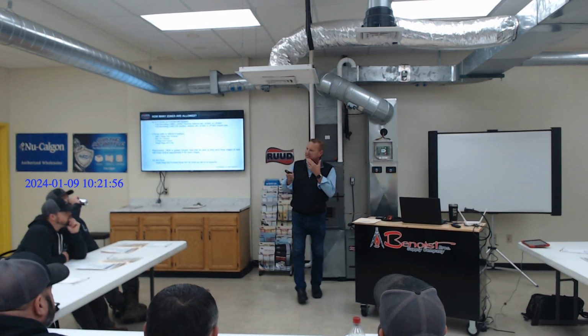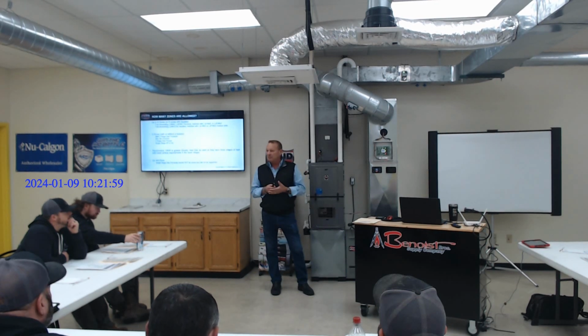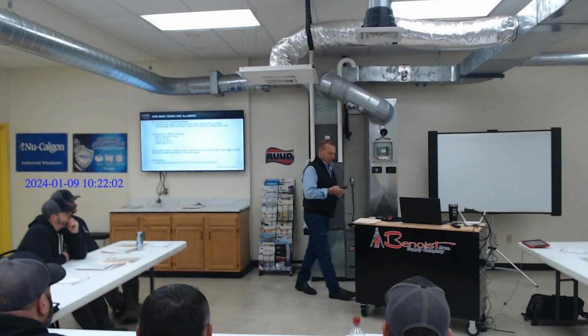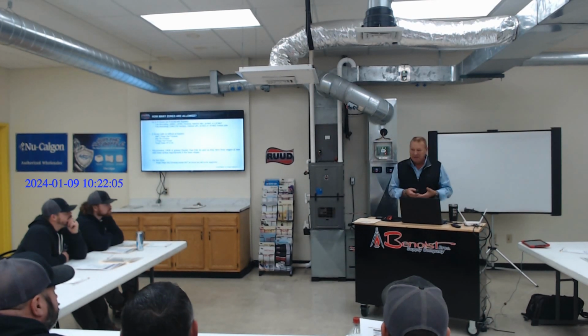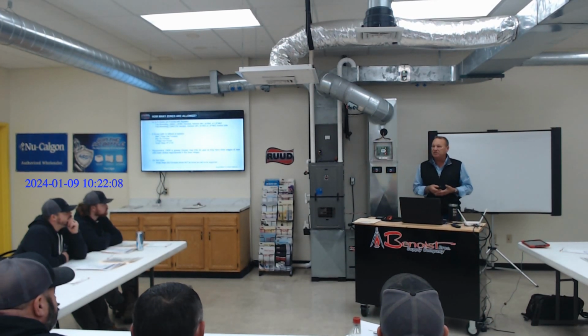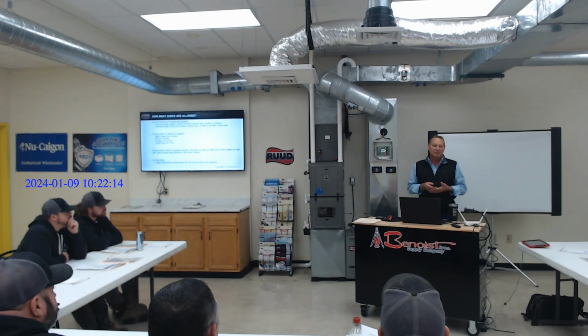Okay? And the reason I can use a contactor on the mid-tier and I have an inverter board is because now on the mid-tier product, I'm manipulating the hertz. I'm not manipulating the voltage. So when that goes into 100%, I can't have more than 2 zones on that system because I go to full capacity. And we'll go into 100% on the mid-tier below 32 and above 90. Did they change that to above 92? It snaps to 100% on the mid-tier product. So once I hit 30 degrees or whatever, needs a call, it's probably going to snap to 100% capacity on the mid-tier heat pumps. Same on the air conditioners, just different temperatures, but most of the time it's heat pumps.